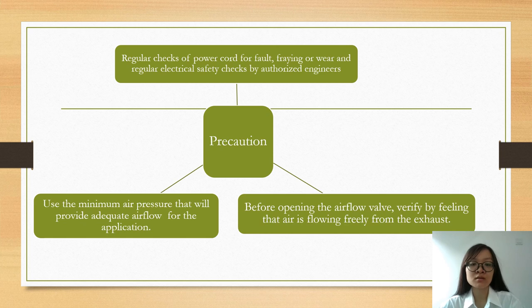Besides, use the minimum air pressure that will provide adequate airflow for the application. Furthermore, never block the air hose to pressurize the vessel. If the vessel exhaust becomes blocked, pressure can build up and possibly shatter the vessel and endanger personnel.